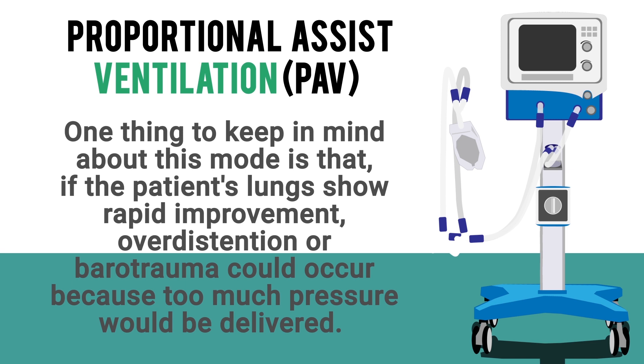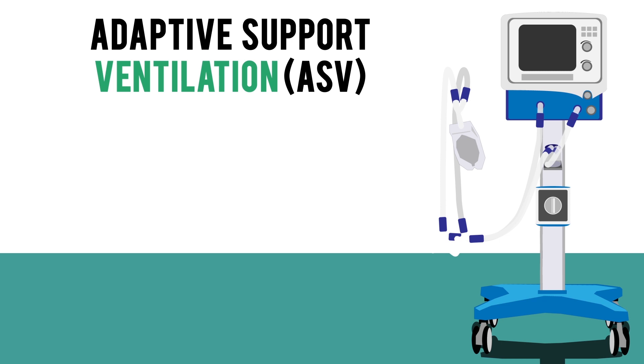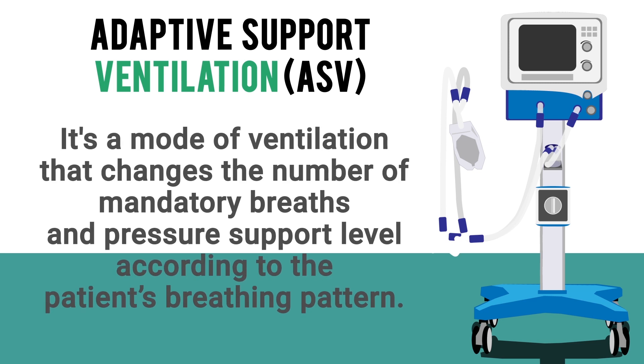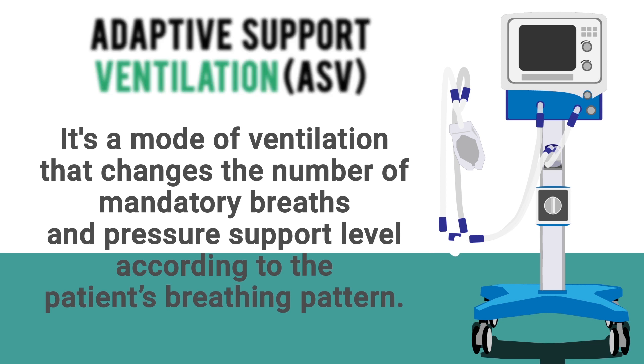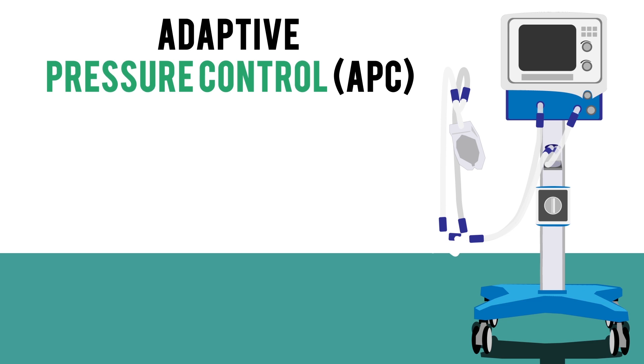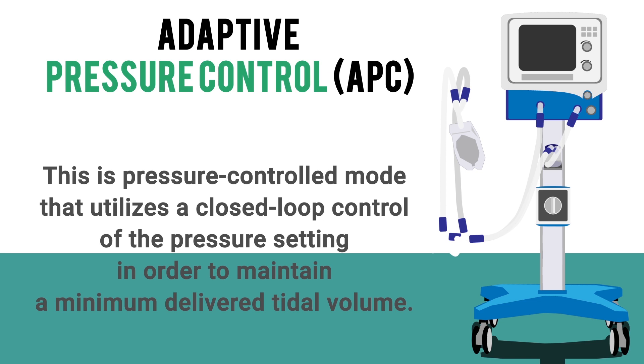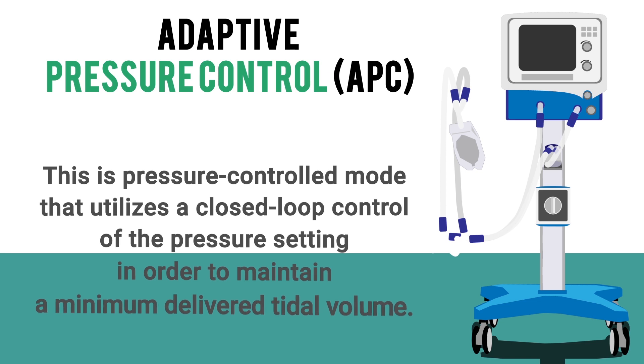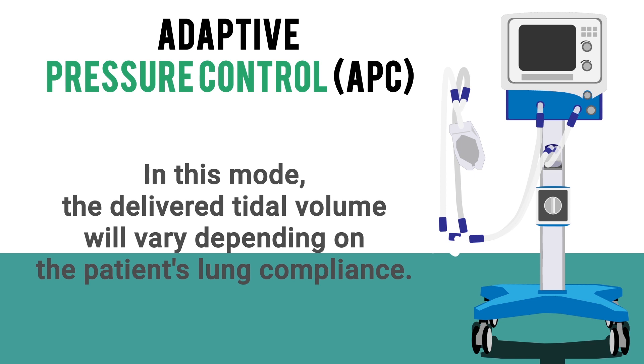ASV, or Adaptive Support Ventilation, is a mode that changes the number of mandatory breaths and pressure support level according to the patient's breathing pattern. APC, or Adaptive Pressure Control, is a pressure-controlled mode that utilizes a closed-loop control of the pressure setting in order to maintain a minimum delivered tidal volume. In this mode, the delivered tidal volume will vary depending on the patient's lung compliance.